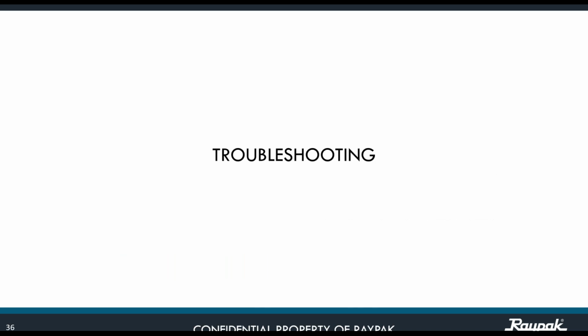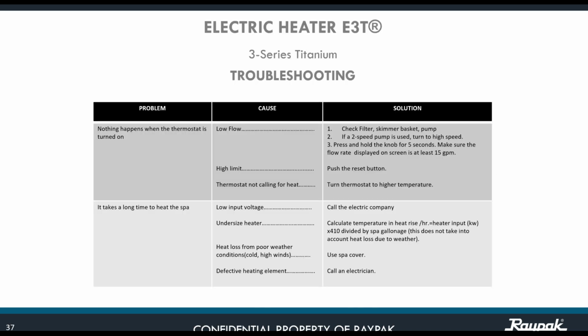Let's start with the troubleshooting. Let's see the first problem. Nothing happens when the thermostat is turned on. The first cause of that problem might be low flow. Check your filter. Check that the filter has been properly backwashed.